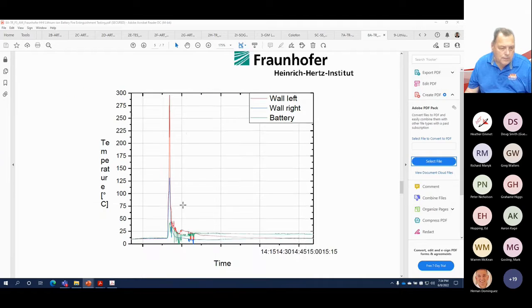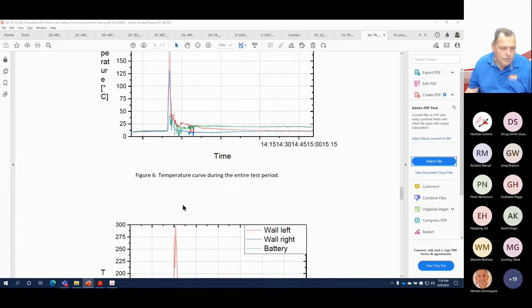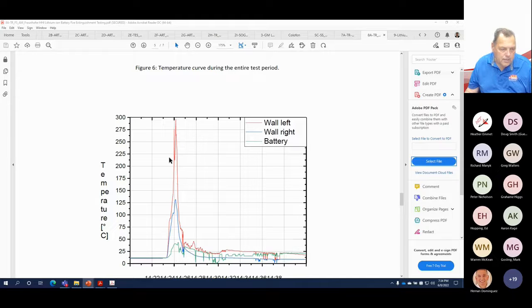Here are the thermocouples, but I think this is quite interesting too, because this was the heat of the battery right here, and this blue line was the right wall, and the red line was the left wall. So the battery was more towards one side, but you can see in all cases, not only are we hitting the thermal decline in temperature and the rapid decline on the battery, but also the radiant heat, boom, down on both sides. And the radiant heat continues to fall. Even though we've extinguished and shut everything off, your radiant heat still goes down.